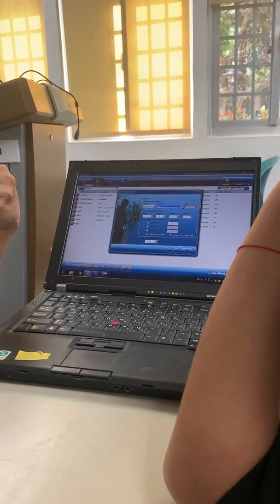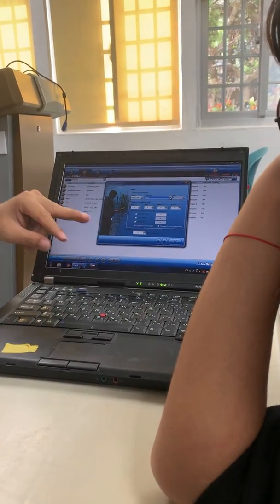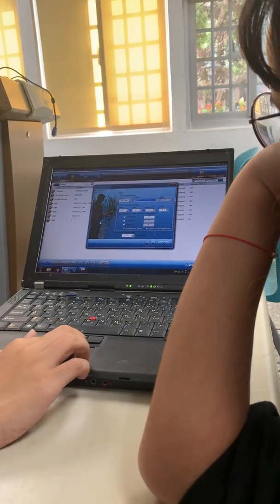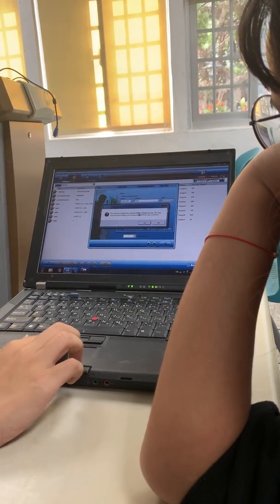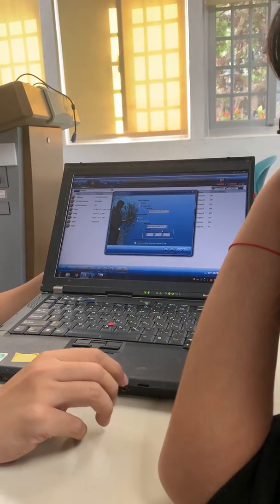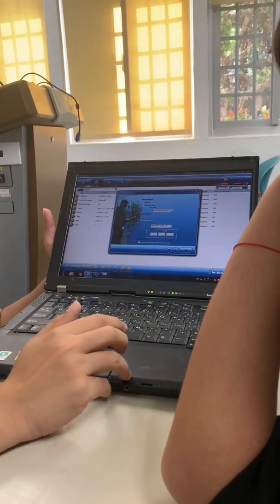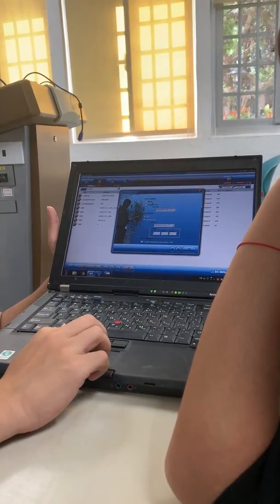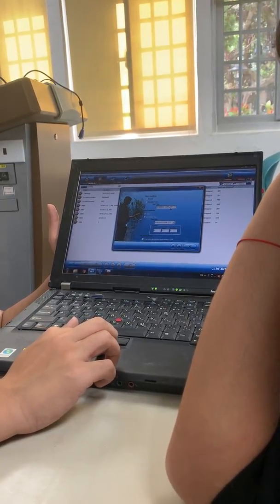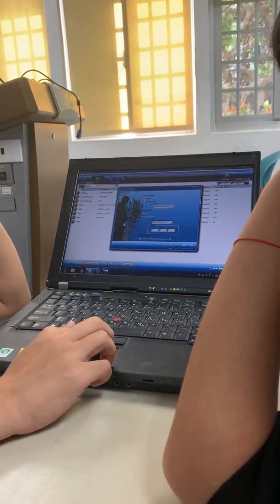So the actual saved sampling rate is 2 seconds — that is the smallest sampling rate for the Level 2. For start mode, there are two options: manual (by hand) and scheduled start. I suggest you use manual, because scheduled start can cause errors if you set AM or PM incorrectly. If you make that mistake, you will not record anything.